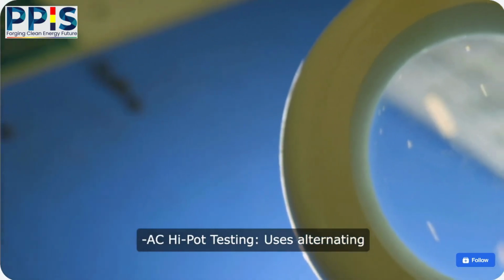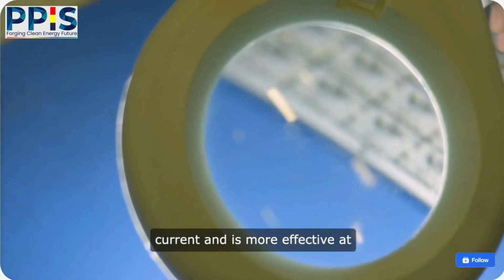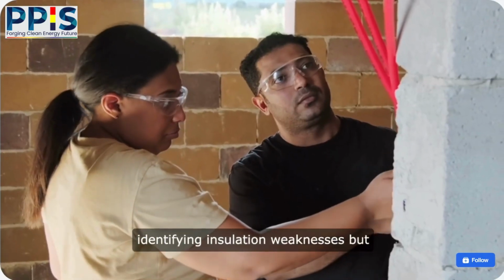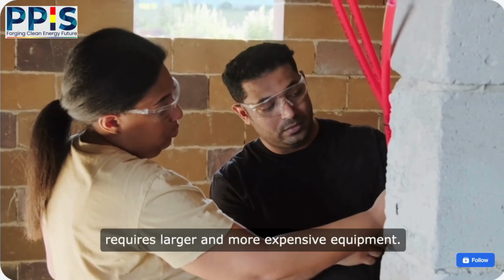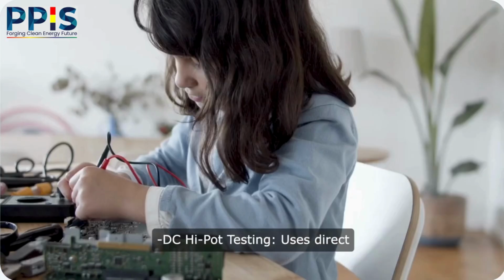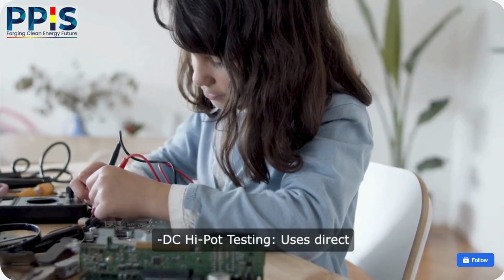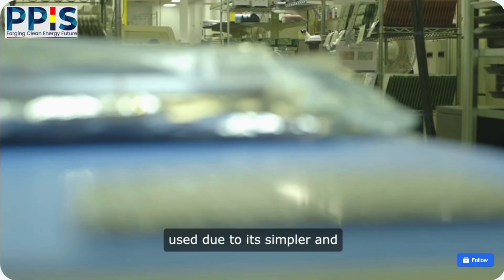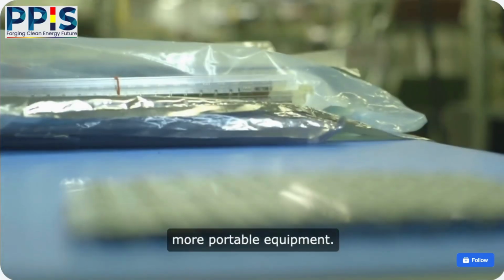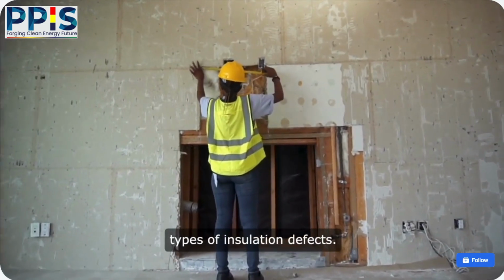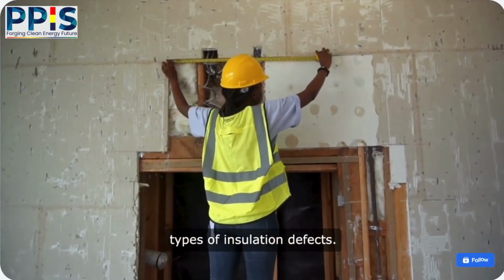AC high pot testing uses alternating current and is more effective at identifying insulation weaknesses, but requires larger and more expensive equipment. DC high pot testing uses direct current and is more commonly used due to its simpler and more portable equipment. However, it may not detect all types of insulation defects.